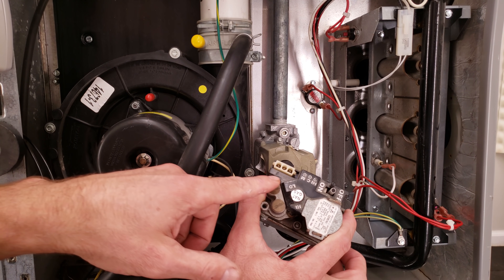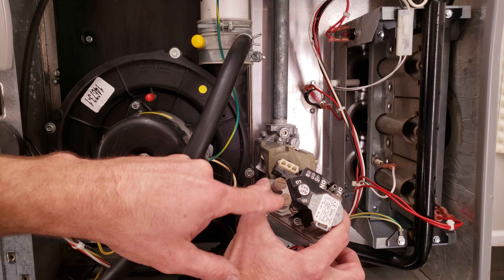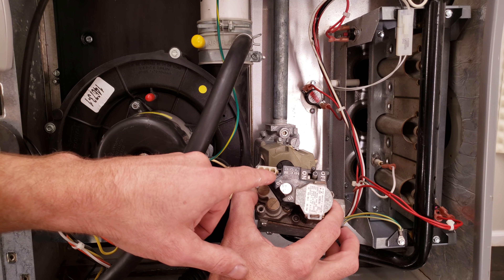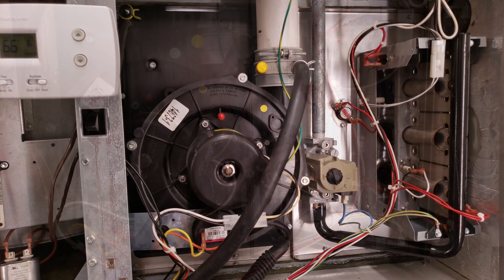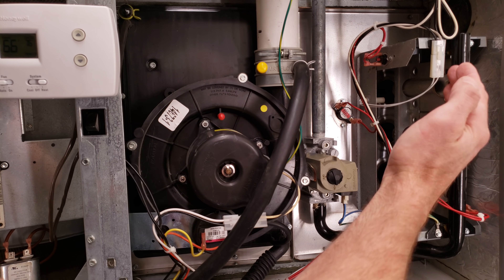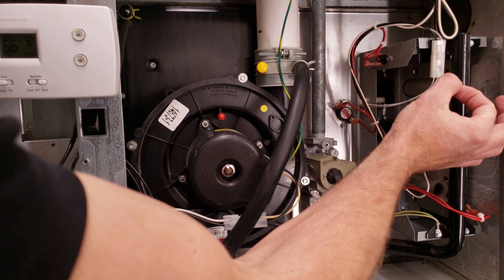This one is a two-stage gas valve because it has a common, low, and high, and it has two brass screws because there are two springs inside. You may also have completely modulating gas valves in higher efficiency furnaces. The combustion chamber is sometimes sealed and sometimes open — on all 80% efficient furnaces it's going to be open; on some 90% efficient furnaces you're going to have a sealed box with a little peephole inside.